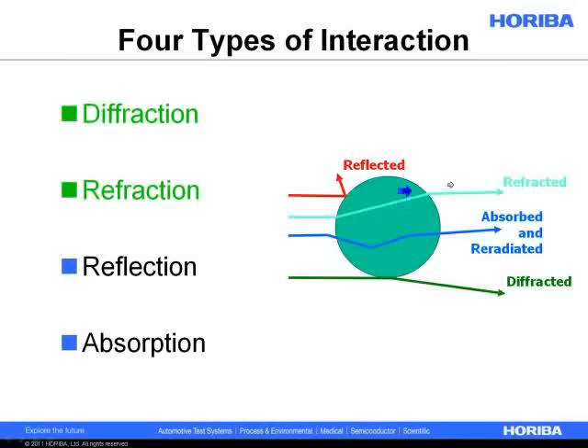Refraction becomes important when the particle size becomes smaller — some multiples smaller than the wavelength of light. That's where the light passes through the particle, changes angle a few times, changes intensity a few times, and we can collect that information as well. We don't like reflection and absorption simply because it's where we lose the signal. Reflection is where the light hits the surface of the particle and reflects back — an easy mental example is something like gold dust. This has very little meaning for size.